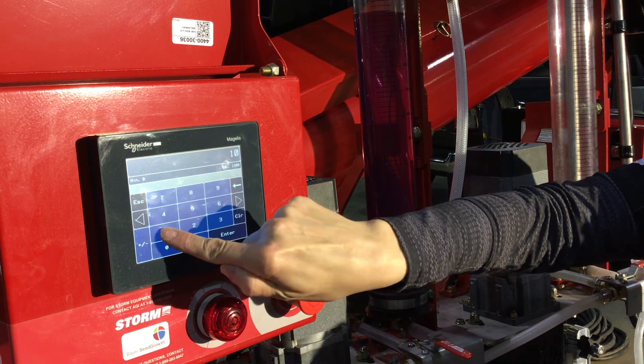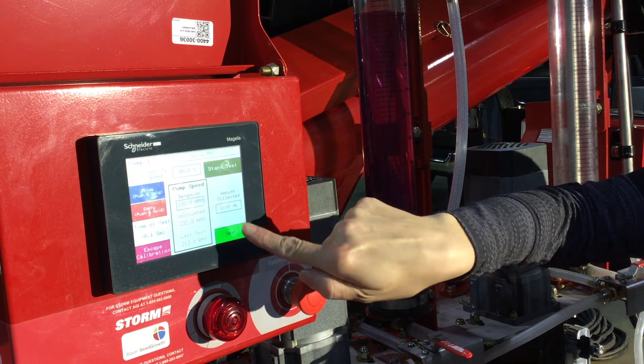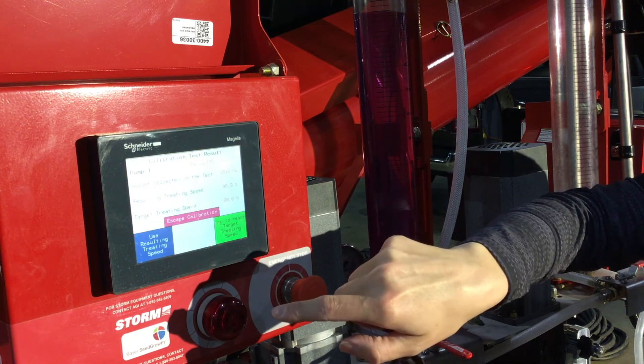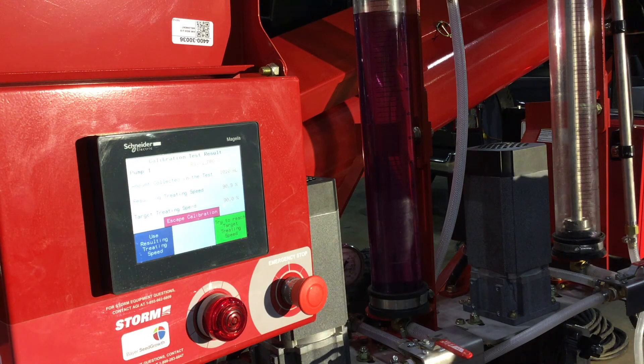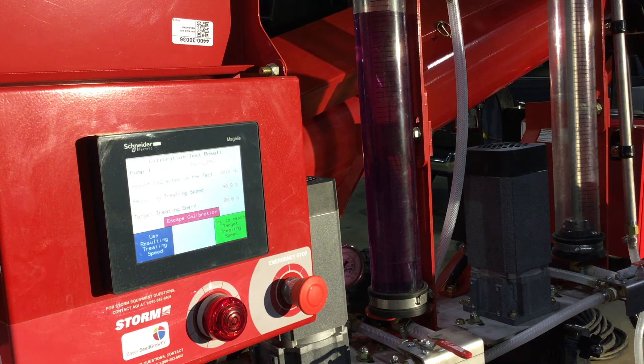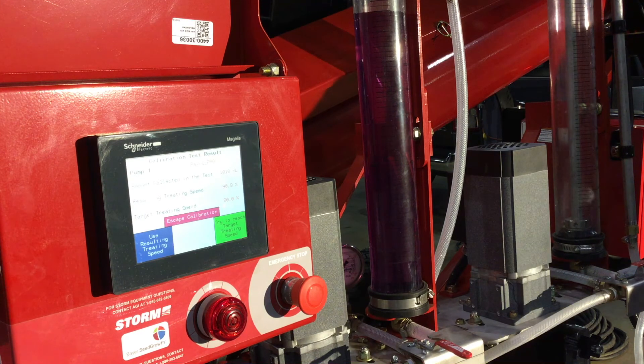We've now hit the 1,000 milliliter mark, or just over — 1,010. Hitting the next button: our resulted treating speed is 90.9% and our target treating speed is 90%. From here, you can either choose again from one of the three options of escaping, using the resulted treating speed, or trying to reach the target treating speed.